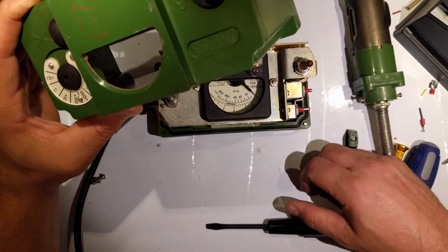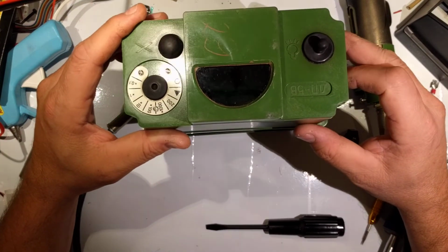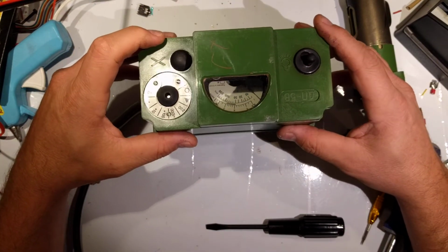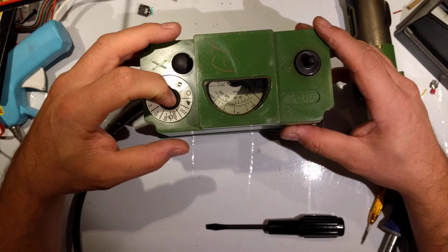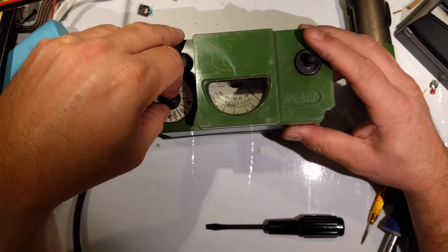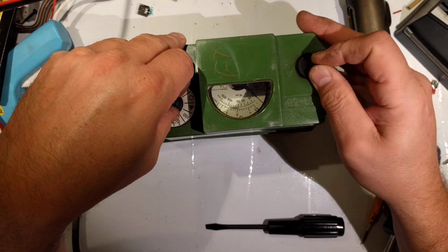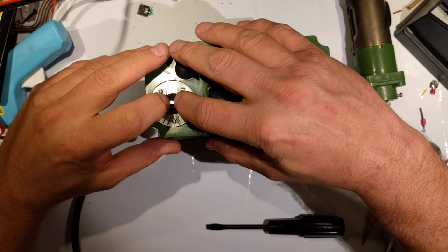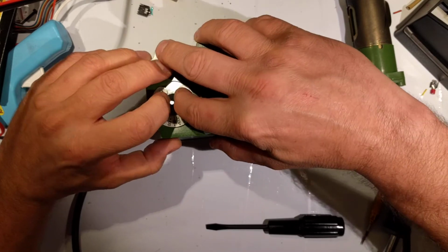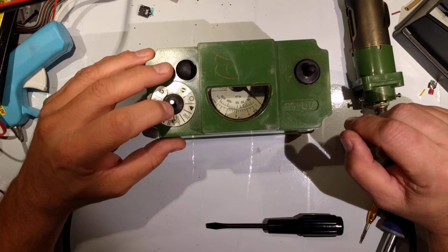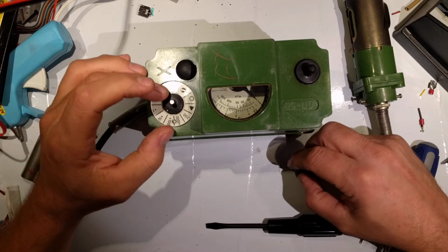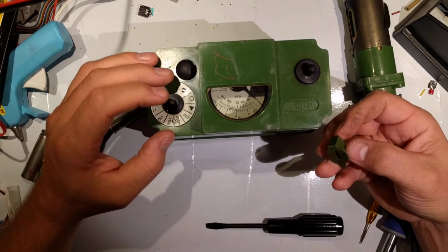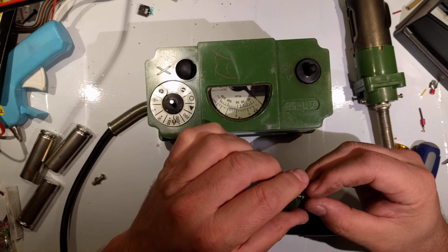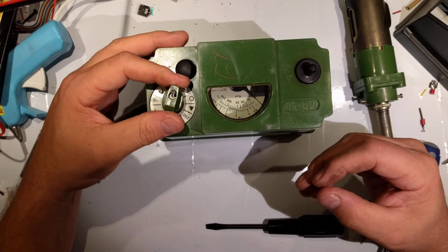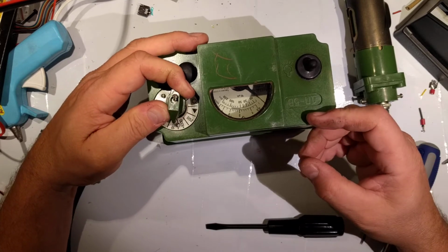calibration. I have actually tested this versus other Geiger counters I have, and even after 30 years, or almost 30 years, 29 years, this thing is pretty close. The standard on a Geiger counter is usually right about, should be within 10% ballpark on most of these meters. If you can get it within 10%, you're considered golden, because with radiation, it's not always going to be a constant. And you're just trying to get a ballpark measurement anyway, especially when you're dealing with something like a Geiger counter and not a scintillation detector. Those are a bit more accurate, and that's indexed.